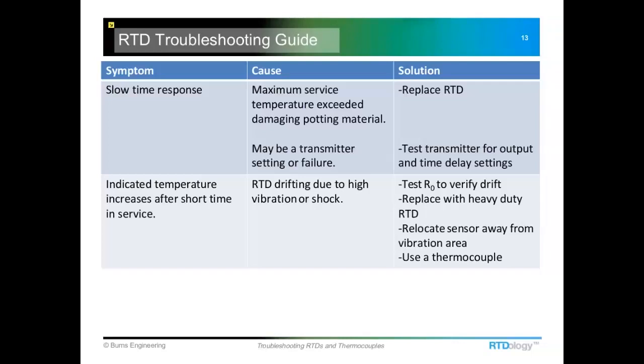Transmitters — especially new programmable types — often have a setting for a measurement delay. The default is typically one second, but you can set it up to 60 seconds or even longer. Some wireless ones have even longer range settings where it will just delay taking a reading from the temperature probe. So that can cause what appears to be a slow response problem.